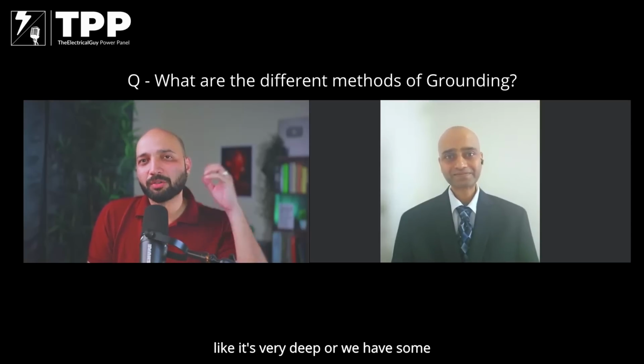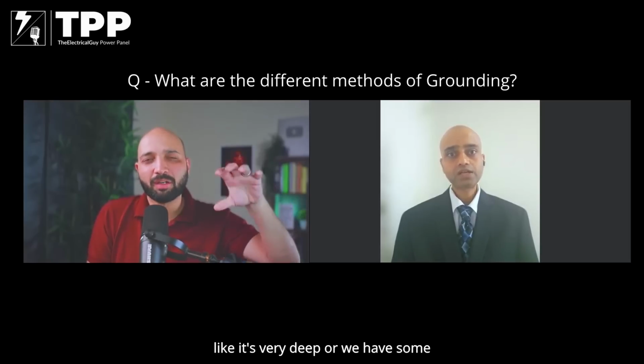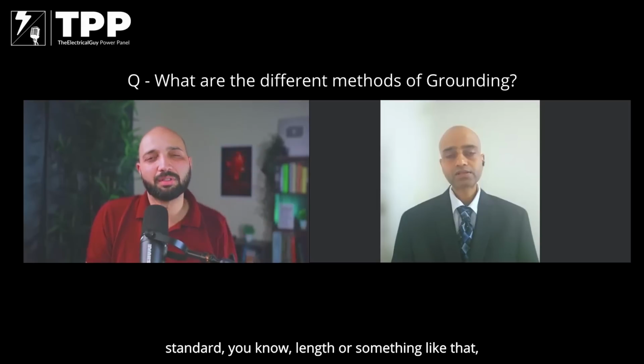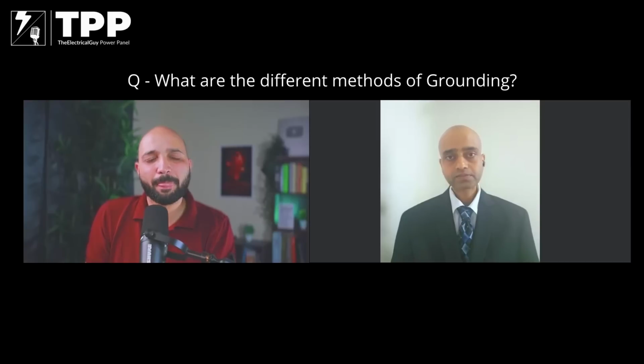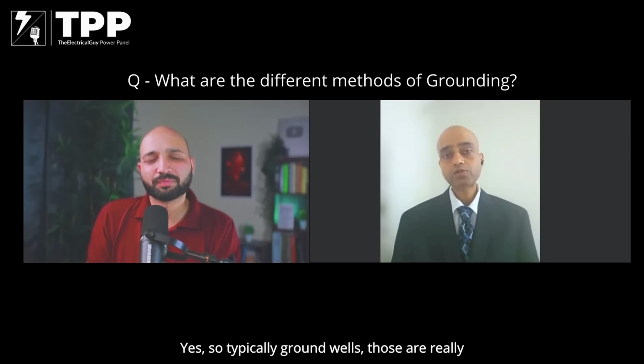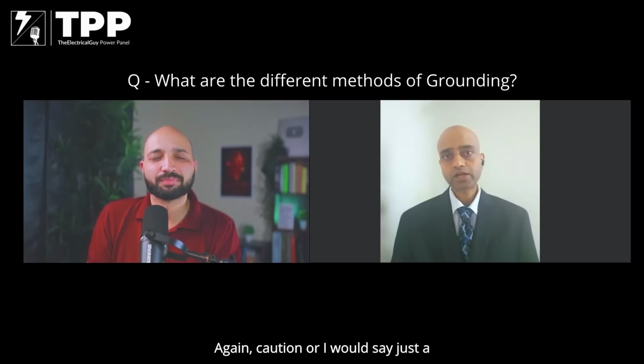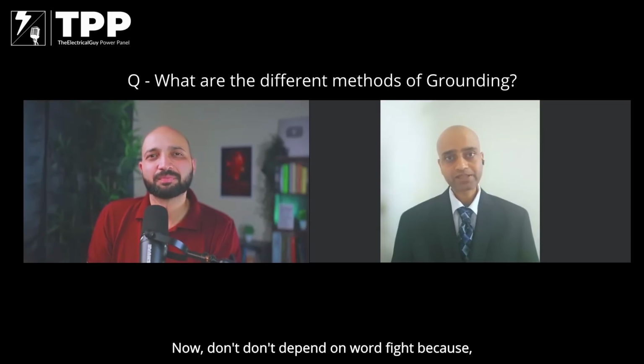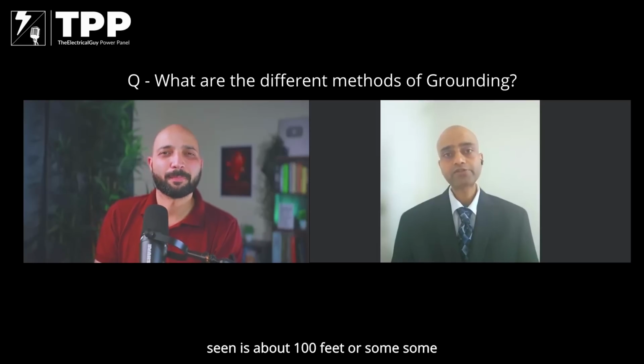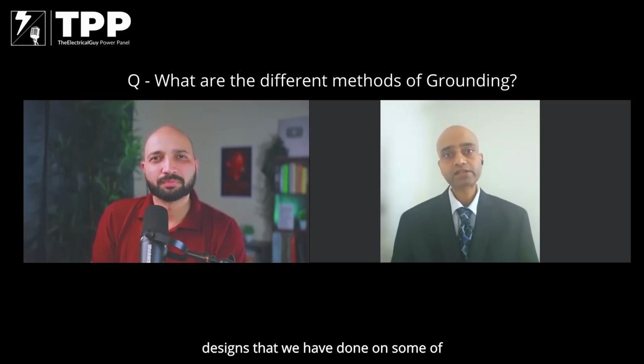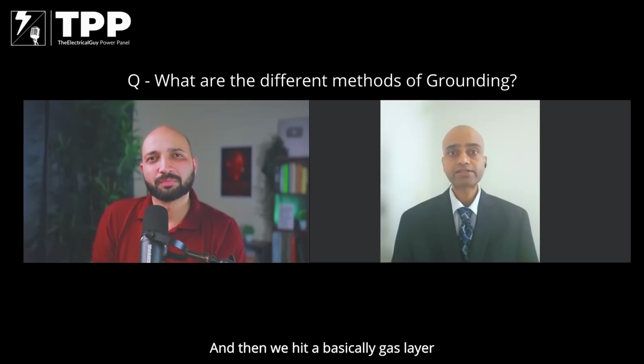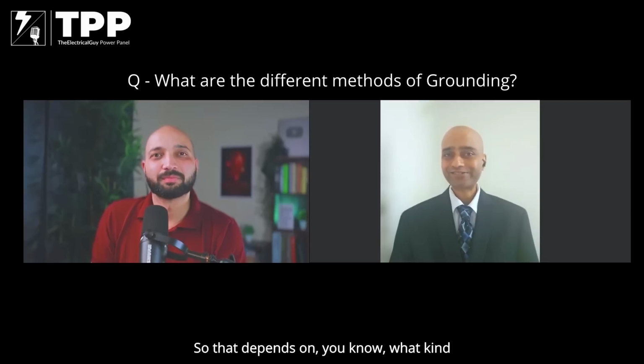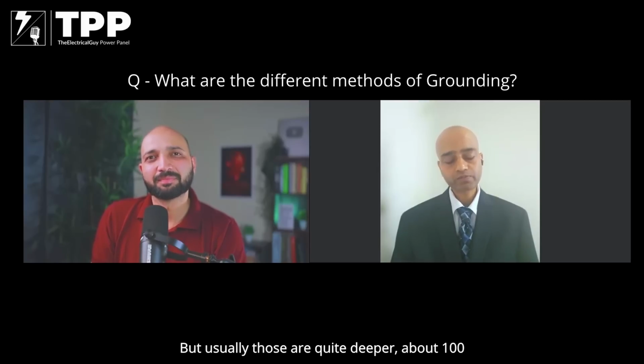So when you say ground well, is it very deep, or do we have some standard length for that? Yes, typically ground wells are really costly because those have to be dug deeper, just like a regular water well. This depends on the soil composition. Don't take my word for it, but most designs I have seen are about 100 feet. Some designs on projects I reviewed were about 150 feet deep, and then we hit a gas layer below it. So it depends on the geology, but usually those are quite deep, about 100 feet roughly.